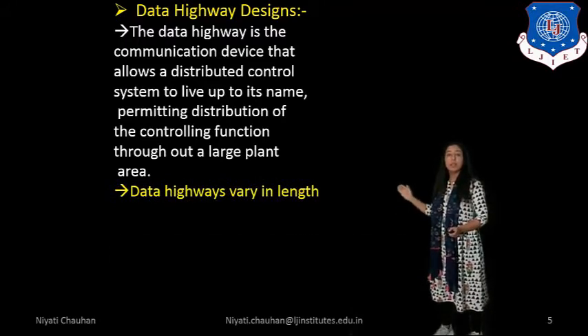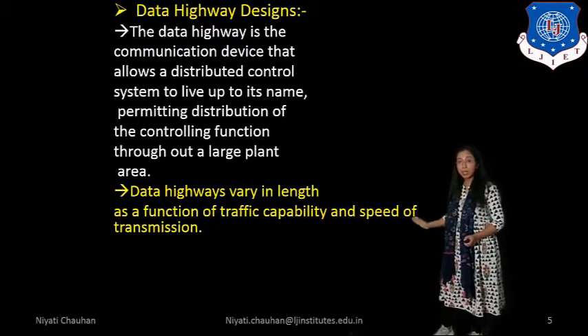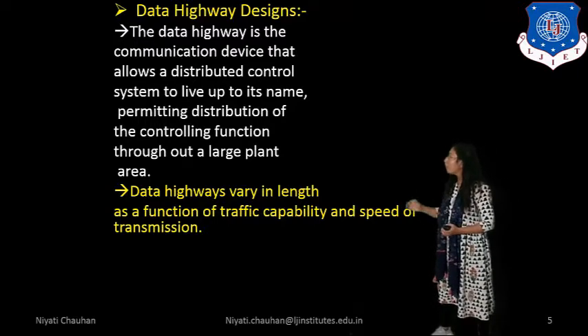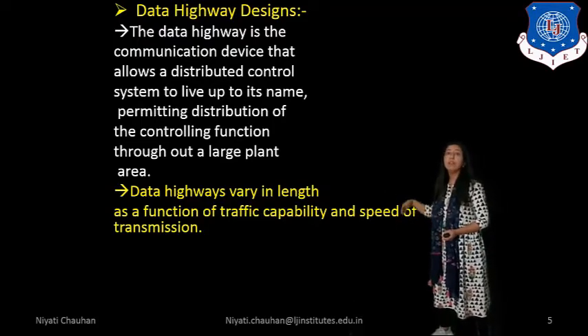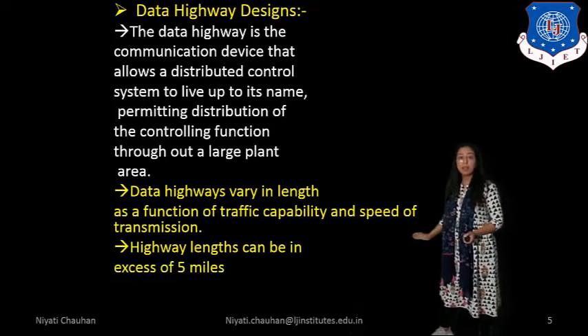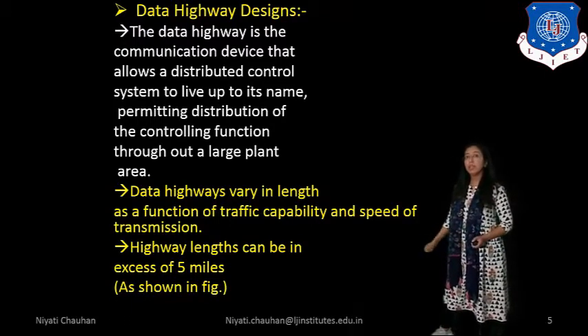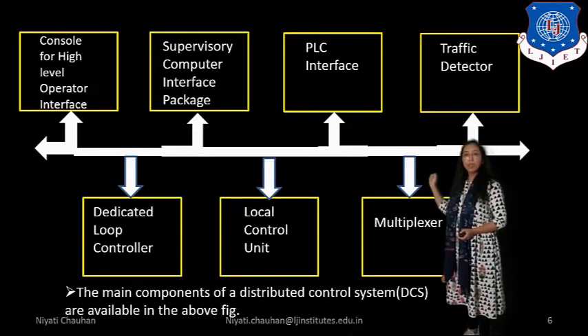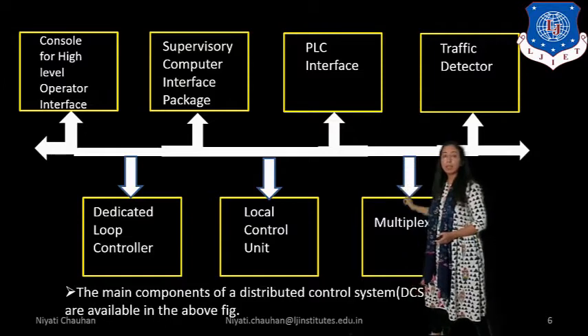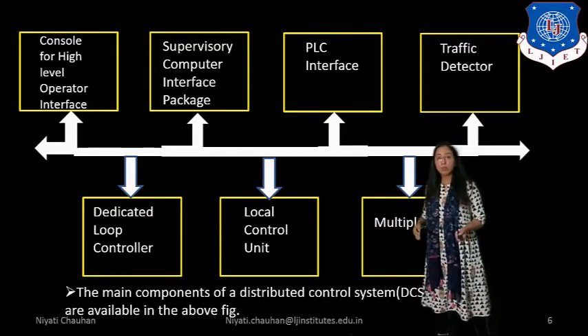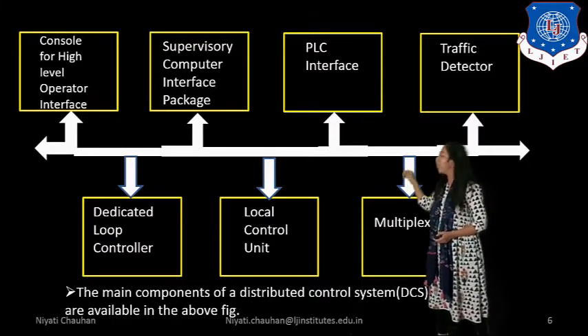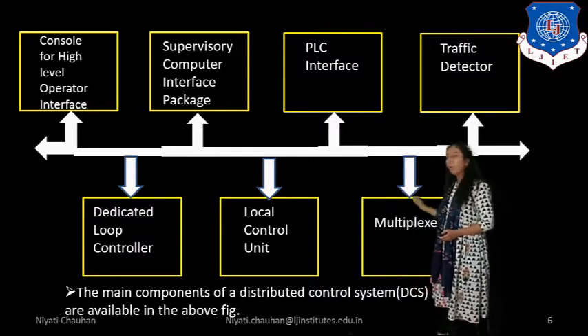Data highway varies in length as a function of traffic capability and speed of transmission. Data highway length can be in excess of 5 miles, as you can see in the diagram. In the diagram, you can see high-level operators interface, supervisory computer, PLC, traffic detector, multiplexer, local control unit, and dedicated loop controller — all devices connected with the data highway. That is why we use a data highway in a distributed control system for communication with all devices.